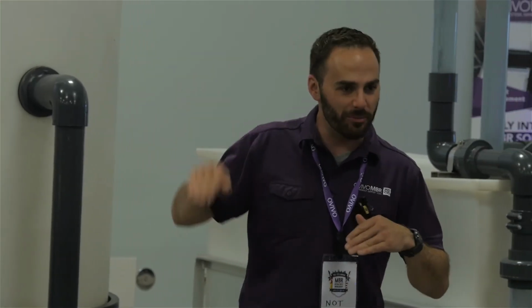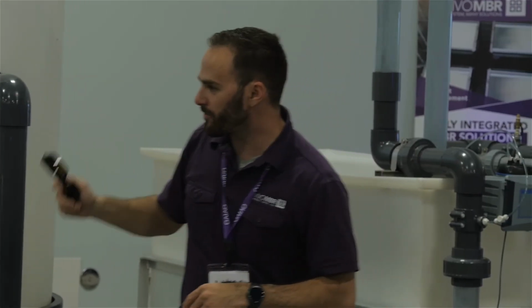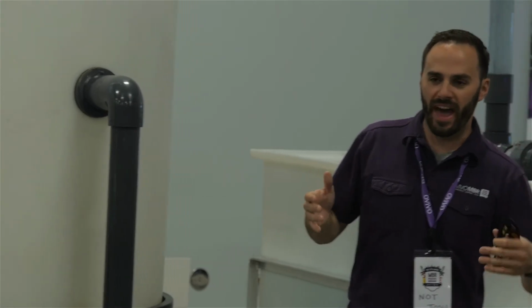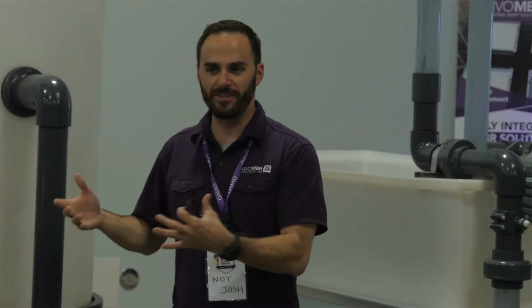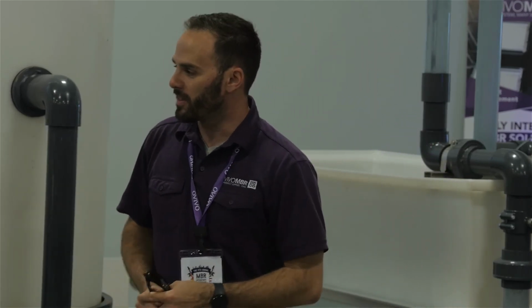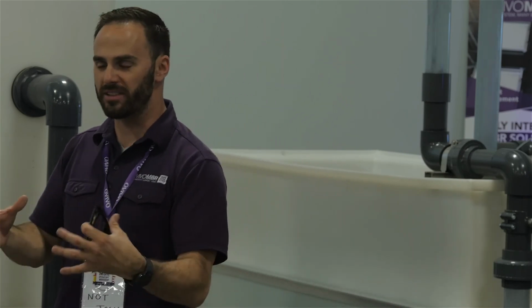The reason for that is, you want to go to the flow meter slide? Sorry, thanks Doug. The reason for that is that the bubbles do not conduct electricity. So the way the flow meter works is it's conducting electricity from one probe to the other. And in doing that, as the flow increases, it has an effect on the reading that thing gets. And it's set up and calibrated that way so that you can get a flow reading just using electricity. When you have bubbles going through there and it keeps interrupting that electrical signal, you get readings that look like that.